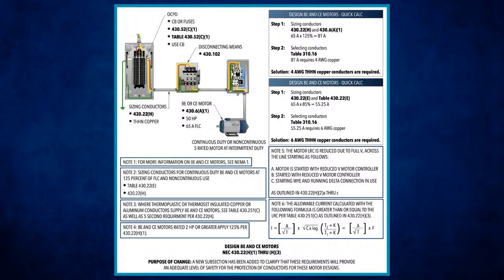But let's just say I'm going to size an inverse time circuit breaker. It's a squirrel cage motor. We'll say it's 50 horsepower, 460 volts, 3-phase, and we're going to do a design B motor. Okay, make it quick. All right. And the same principle is going to fall here that I'm looking at in this calculation. So let's say you go over now, and I'm going to start you through a code loop of how to do all this. So in order to get all this started, I need to go over and look at 240.4G.